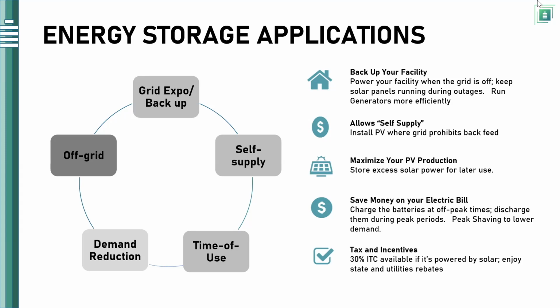We have time of use. For my California folks, they're very familiar with time of use. For those not familiar, the utility charges you twice or even sometimes 3 times the amount of power during peak times. So how we use batteries here is discharging the battery during those peak times, using that as an avoided cost solution. Instead of paying 50 cents a kWh in San Diego for power during the dinner hour, why not just discharge the battery during that dinner hour for the critical loads? You can use that to avoid those costs and reduce your electrical bill.